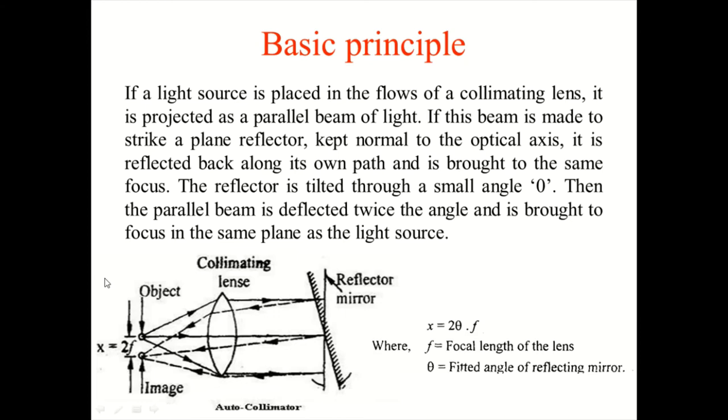If the beam is made to strike a plane reflector kept normal to the optical axis, it is reflected back along its own path and is brought to the same focus. The reflector is tilted through a small angle theta, then the parallel beam is deflected twice the angle and is brought to focus in the same plane as the light source.